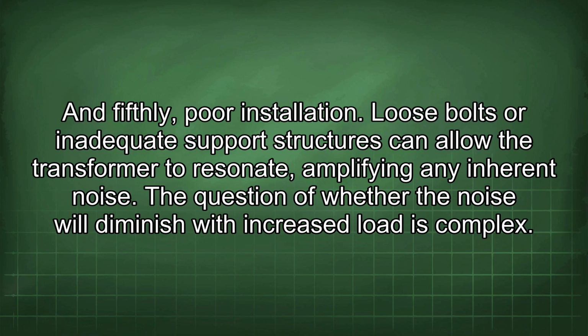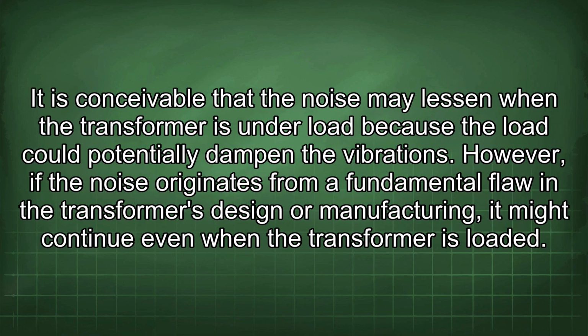The question of whether the noise will diminish with increased load is complex. It is conceivable that the noise may lessen when the transformer is under load because the load could potentially dampen the vibrations. However, if the noise originates from a fundamental flaw in the transformer's design or manufacturing, it might continue even when the transformer is loaded.